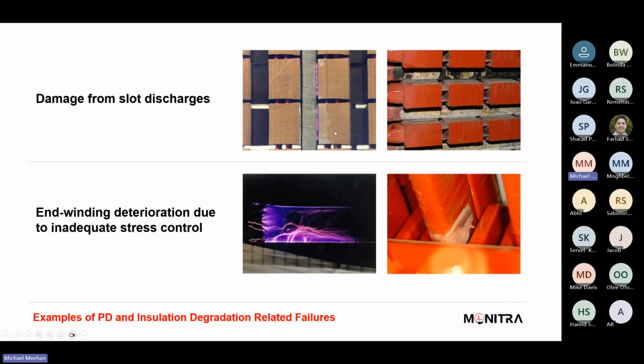These are some examples of what PD actually looks like in machines. These are like from laboratory type pictures, but it just helps with that sort of visualization of how the PD from the windings from the stator itself tries to break the insulation between phases, between ground, and how it'll jump and track. So the picture here is clearly showing you the breakdown between the insulation in the stator core here, and then this is from an end winding, and this could be from vibrations that when the end winding comes out of its slot, that's one of the weak spots.